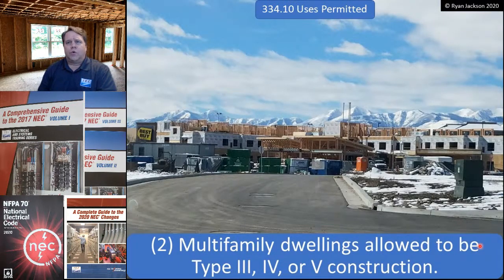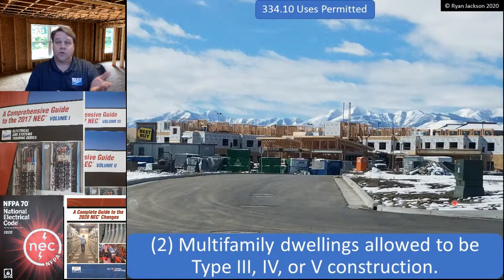It gets a little bit more tricky once we get into multifamily dwellings. Multifamily dwellings, you can use NM cable if the multifamily dwelling is permitted to be type 3, 4, or 5 construction. Okay, we're going to explain types 3, 4, and 5 here in just a minute. And by the way, the other types of construction, of course, are types 1 and 2. And there's an Annex E in the back of the NEC. I don't use it.